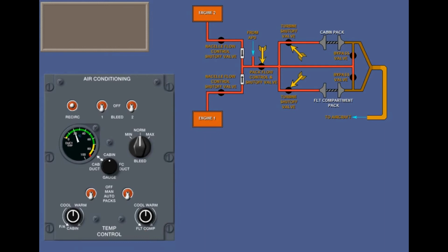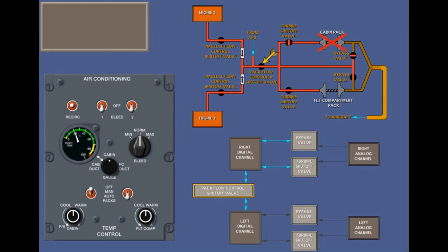Flow to the ACM packs is controlled by the pack flow control and shutoff valve and by turbine shutoff valves, operated by these switches, and of course by the electronics control unit. But what happens in abnormal conditions? Firstly, if there's a problem with an ACM pack, or you switch it off, its turbine shutoff valve will close, and its bypass valve will close. Of course, the ECU digital channel in control will still regulate the pack flow control and shutoff valve, giving normal output. In this situation, even if the recirculation switch is off, the ECU will operate the recirculation fan at low speed.